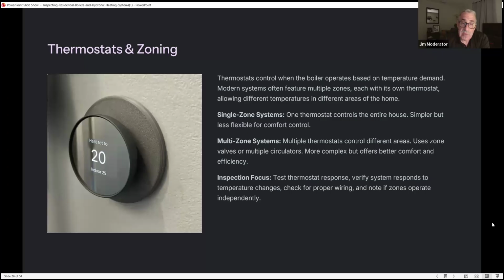So we have our single zone systems, one thermostat that controls the entire house, which I wish I had, but we don't. Simpler but less flexible for comfort. Multiple zone systems: multiple thermostats control different areas, using zone valves or multiple circulators. More complex, but offers better comfort and efficiency. Inspection focus: test thermostat response, verify system response to temperature changes, check for proper wiring, and note if the zone operates independently.